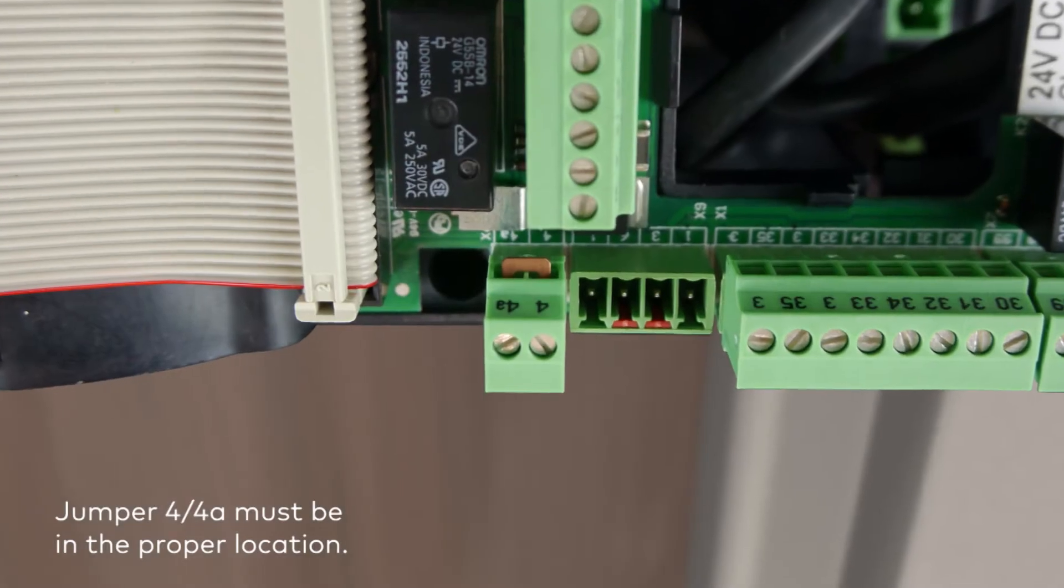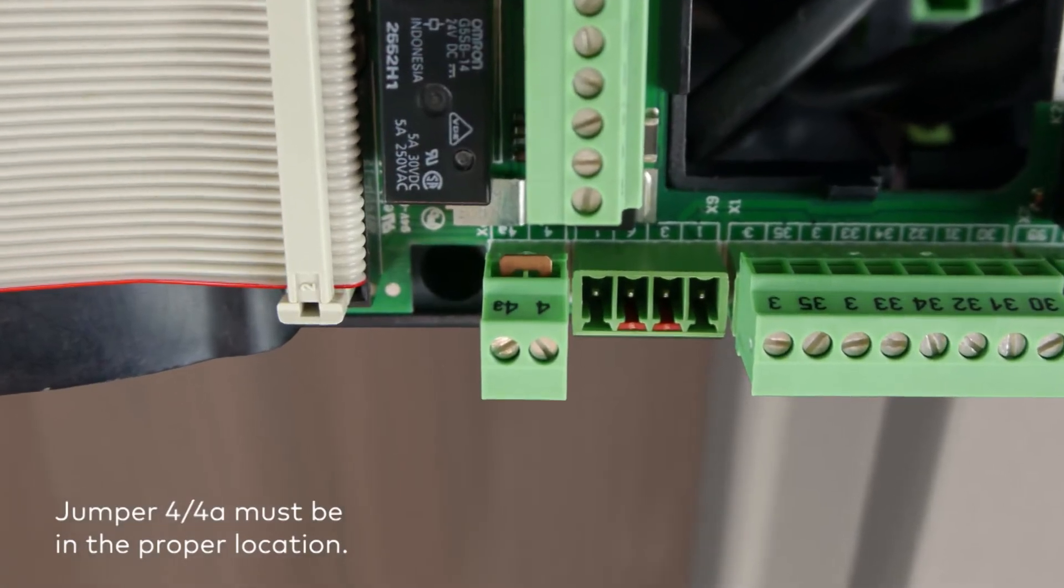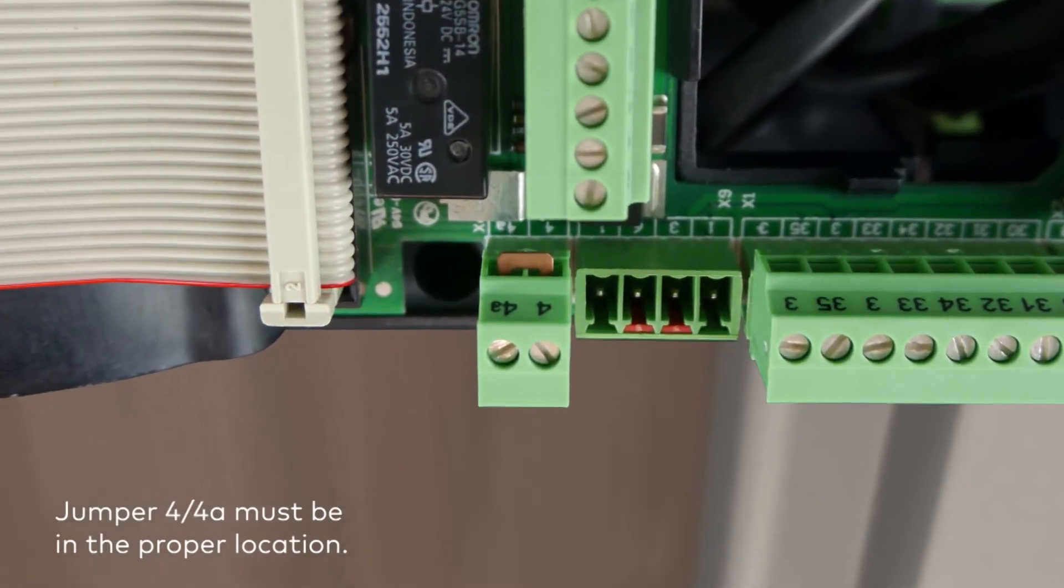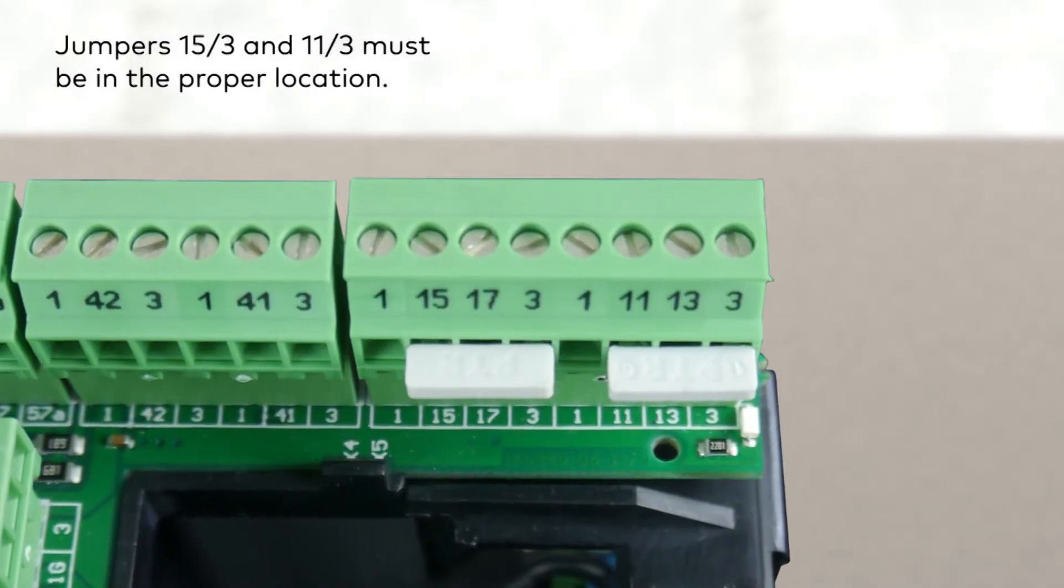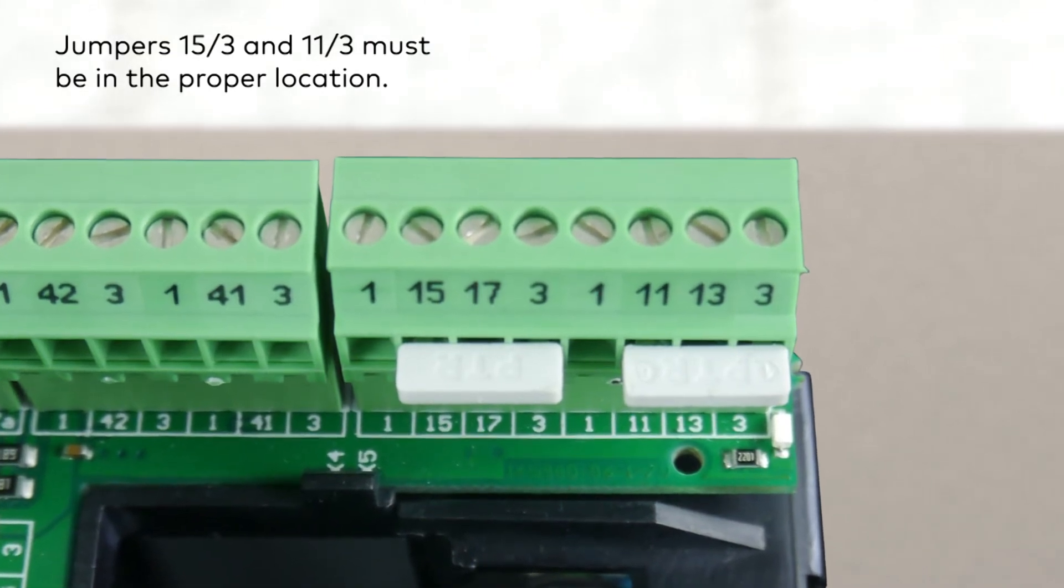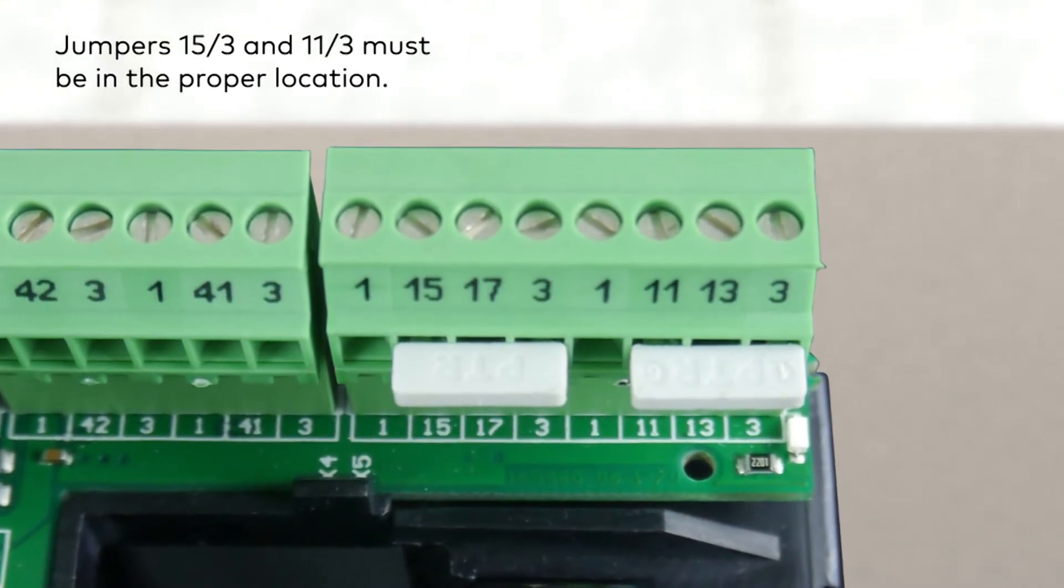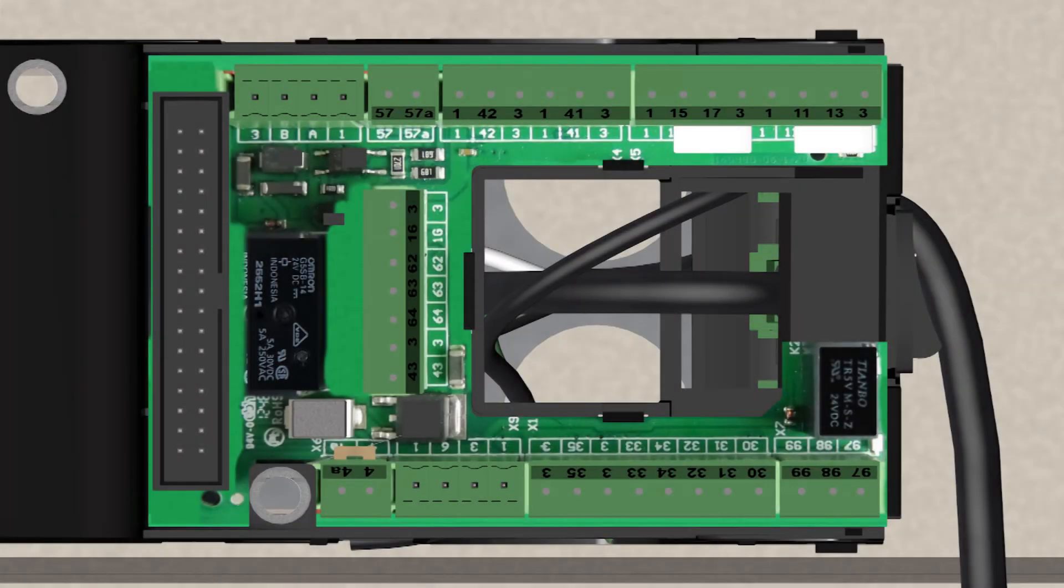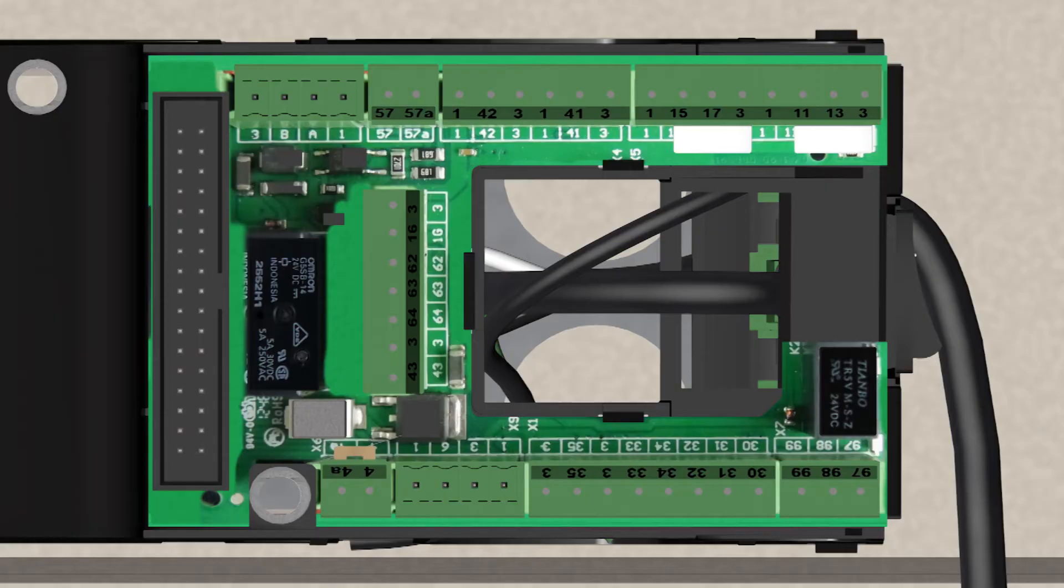The connections at 4/4a, 11/3 and 15/3 are normally closed circuits and the block with the factory jumpers must be installed in the correct location before the operator will move.